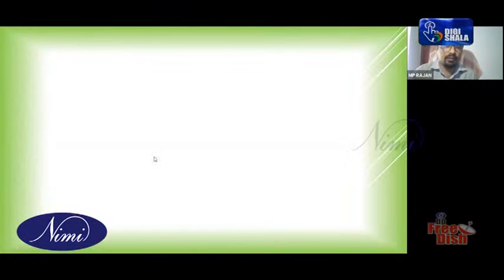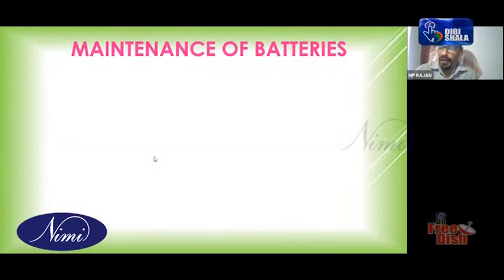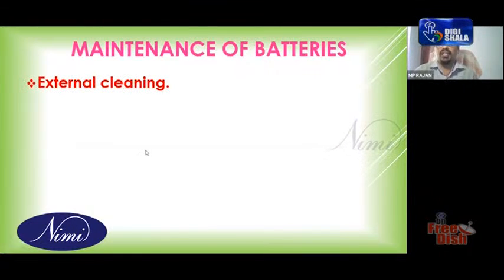Corrosion already explained. And what are the maintenance you can do? External cleaning is very much required, like solar panel. You have to do external cleaning. Whatever the electrolyte portion is there on the terminal, you have to clean it. Dust is there, you clean it. Otherwise, when you open the vent plug, dust may go inside. The electrolyte should contain only the required material like water and sulfuric acid. Extra foreign material will reduce the life of the battery. So pakka cleaning is required.